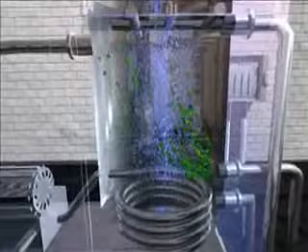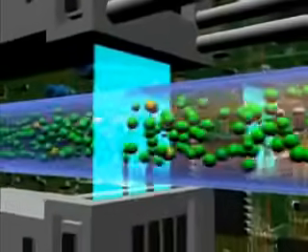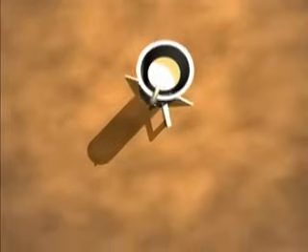In order to completely condense any remaining water vapour and to free the biogas from any suspended matter or silica, the biogas is subjected to a washing and drying process. This is carried out with a vapour at almost freezing point so that the gas is cooled down to a temperature of under 5 degrees centigrade. The biogas is constantly tested with an online measuring system, which records the amounts of methane, hydrogen sulphide, carbon dioxide and oxygen, guaranteeing a high degree of efficiency and security. In case of any overproduction of biogas, it is necessary to operate a gas flare, as unburned methane that escapes into the atmosphere is harmful for the climate.